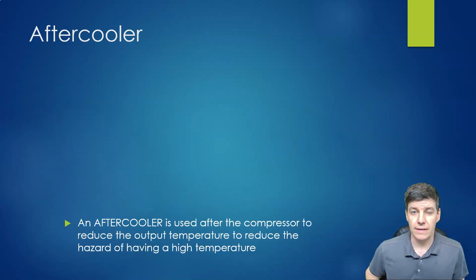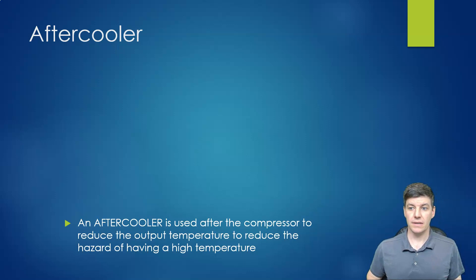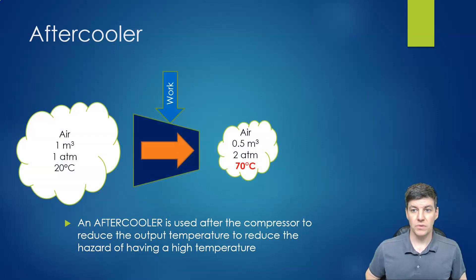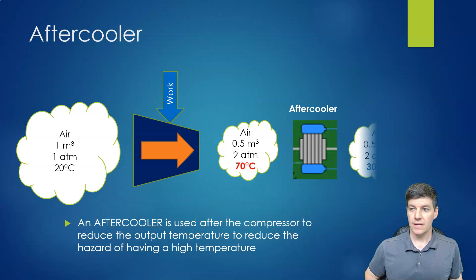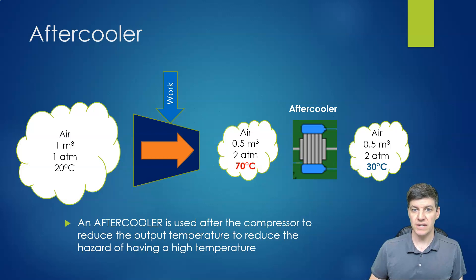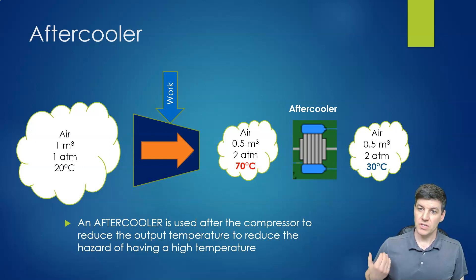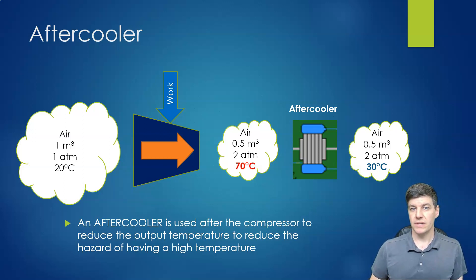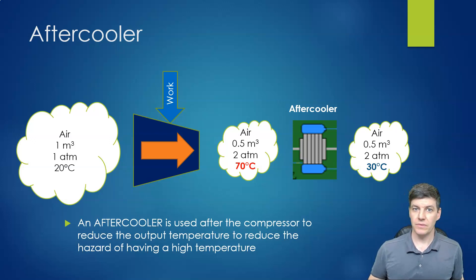So we bring in an aftercooler — something that cools the air after all the compression is done. We go through our compression cycle, hot air comes out, and we pass it through a cooler which reduces that air temperature down to something that is safe. That's the primary role of the aftercooler. In our simulation, ours is water-cooled through a heat exchanger, but sometimes they're air-cooled or other types of cooling.